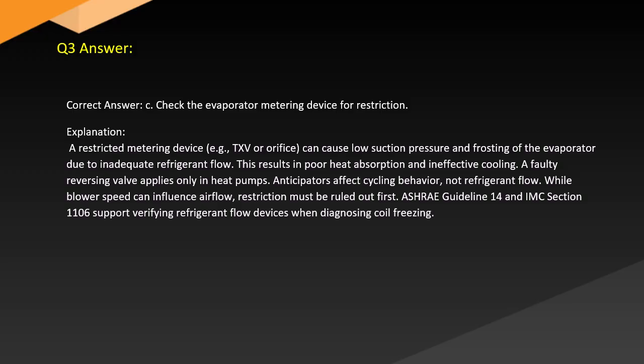Explanation. A restricted metering device, TXV or orifice, can cause low suction pressure and frosting of the evaporator due to inadequate refrigerant flow. This results in poor heat absorption and ineffective cooling. A faulty reversing valve applies only in heat pumps. Anticipators affect cycling behavior, not refrigerant flow, while blower speed can be adjusted, but airflow restriction must be ruled out first. ASHRAE Guideline 14 and IMC Section 1106 support verifying refrigerant flow devices when diagnosing coil freezing.